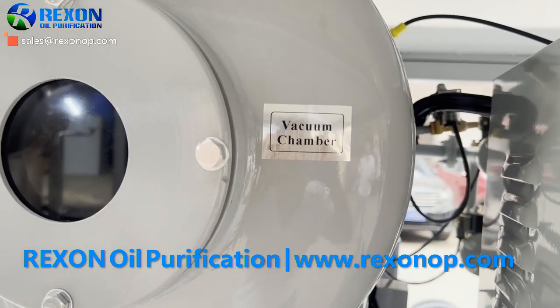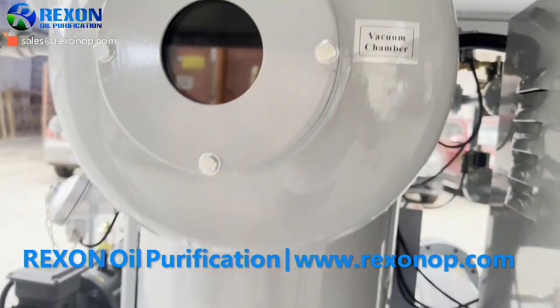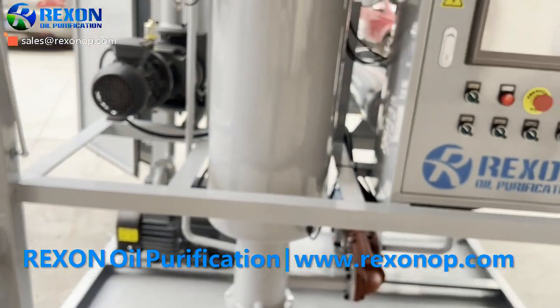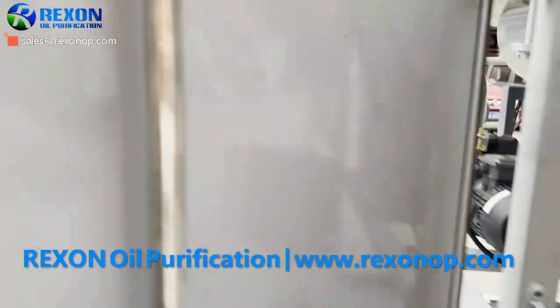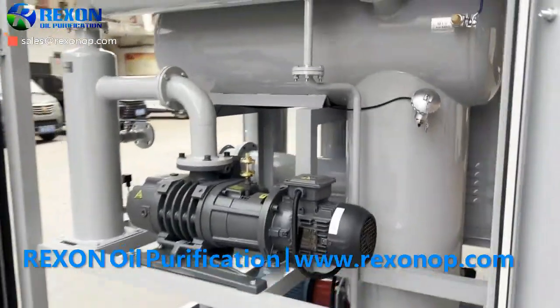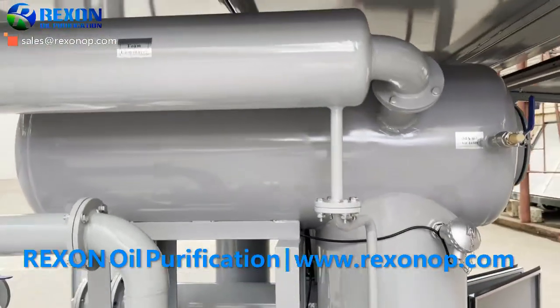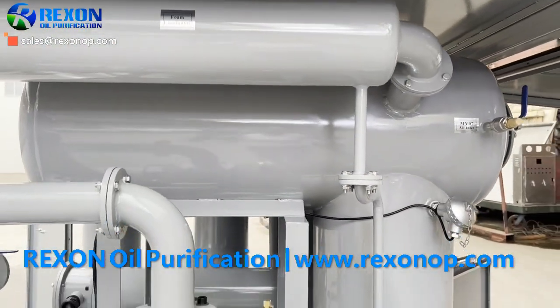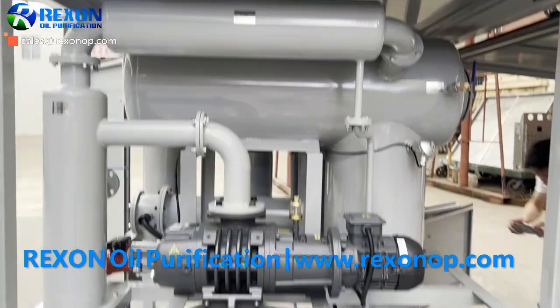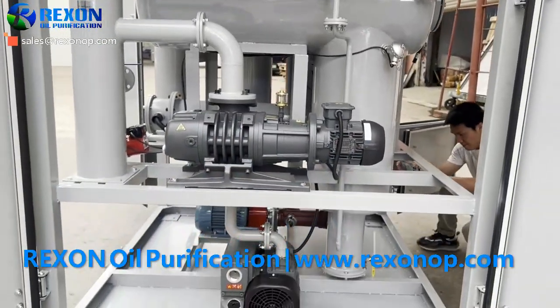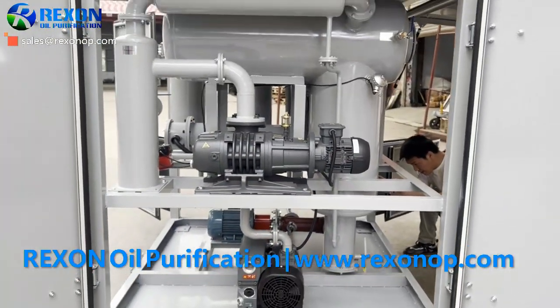And here is the vacuum chamber, which is especially used to dehydrate and degas the transformer oil. It can completely remove the moisture and gas from the transformer oil. After that, the oil BDV value will be improved a lot, to above 75 to 85 kV.